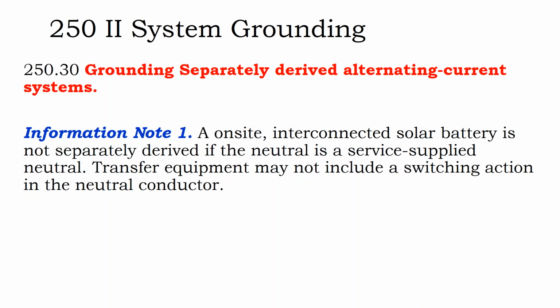Even though your neutral may not be intended to carry current at all times, maybe it's undersized, maybe it's only designed to carry unbalanced loads. But if you have a transfer switch and you want your solar array to be interactive with the grid, it's going to be sharing the same neutral as the grid. You might have a switch that disconnects the grid feeders from your solar array feeders during a blackout, but you may want to switch back onto the grid automatically when the grid comes back on. And so you're sharing a neutral to provide a common reference point for grid interactivity. If you're sharing a neutral, it's not considered to be a separately derived system.